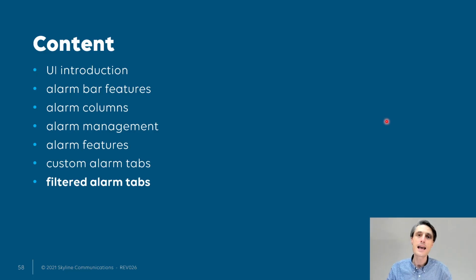So that's how you can easily add custom tab pages to your alarm console. Remember, if you click on the plus sign and you have indexing, you do have the possibility to do a direct search onto your alarm database by just typing a couple of keywords and looking in the last 24 hours. Underneath that, you have the possibility to reopen closed tab pages, and to go for current tab pages, a couple of predefined ones. Remember the linked one to the cards, that's a convenient one. We do have the history fetching we can do, history of the last hour or last 24 hours or something like that, or custom. You need to choose whether to include alarms or information events.